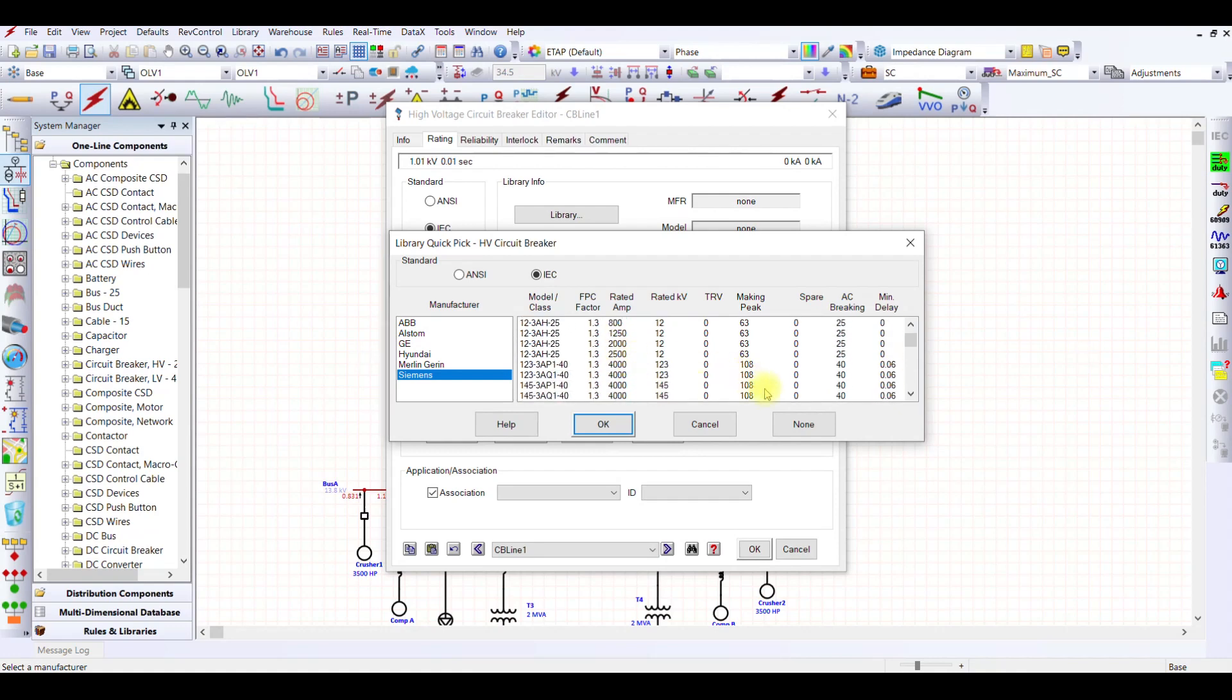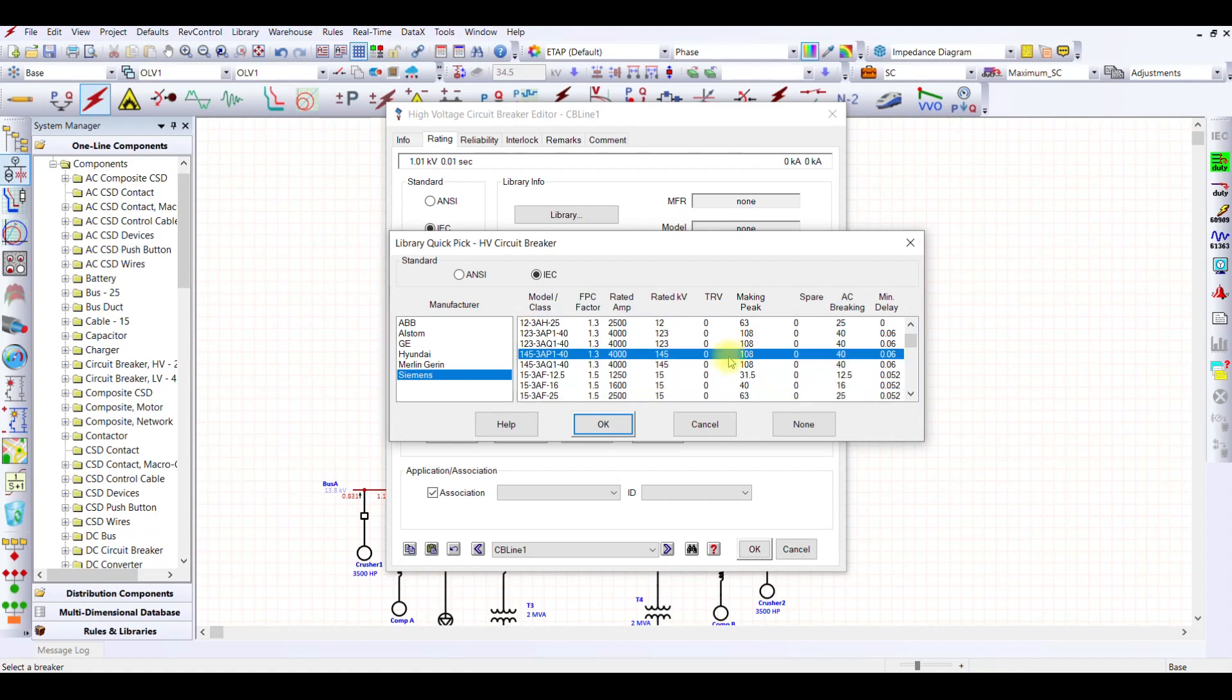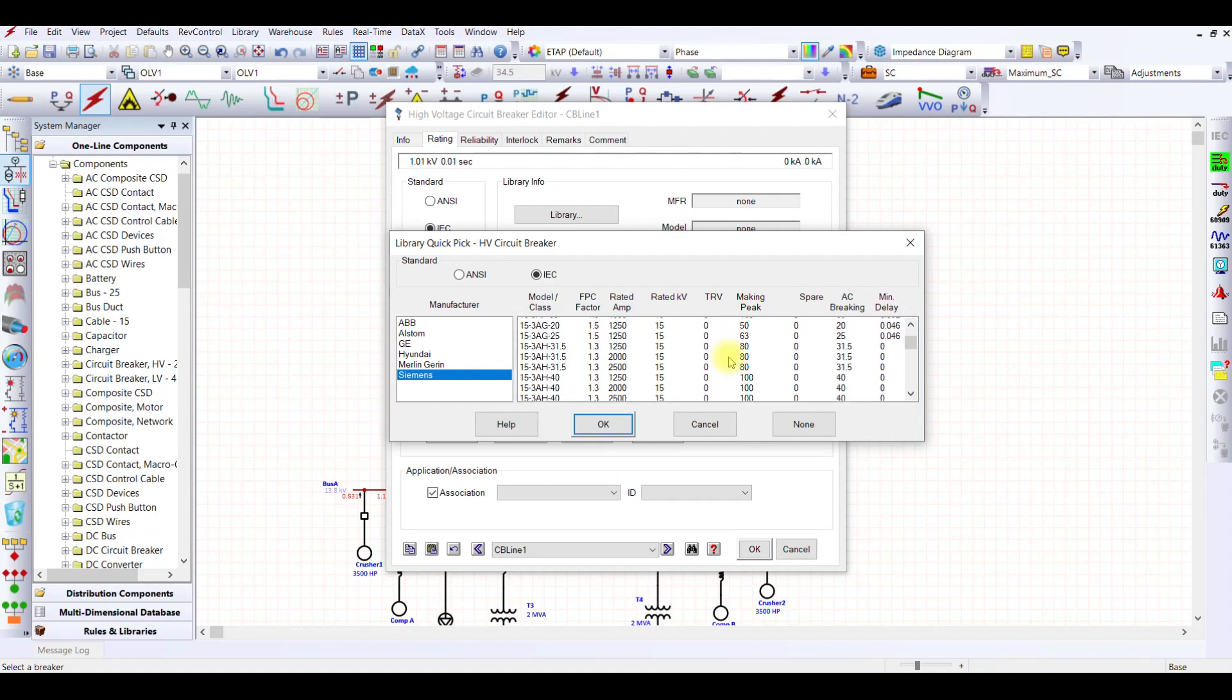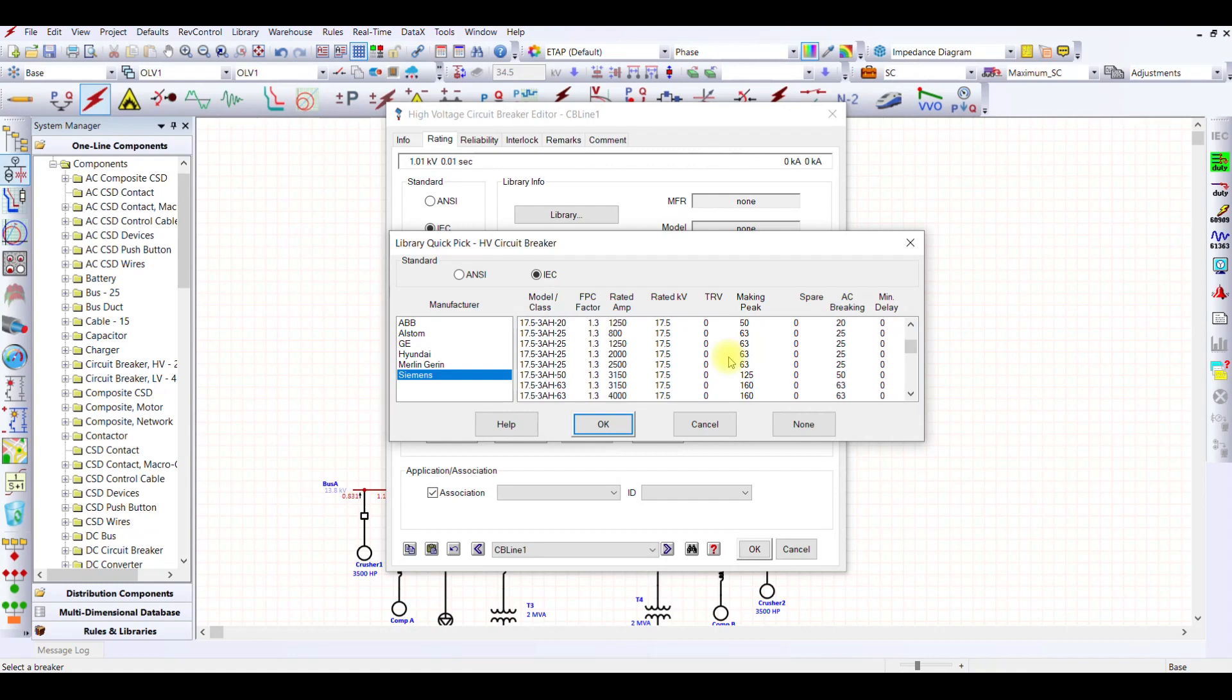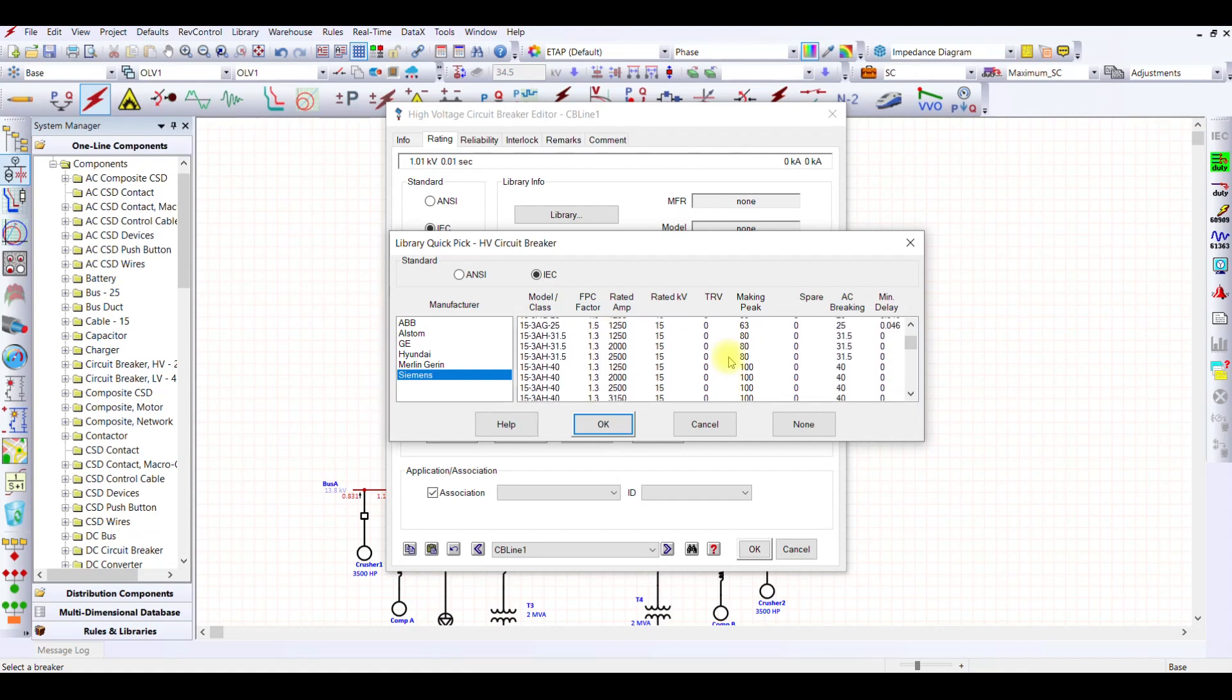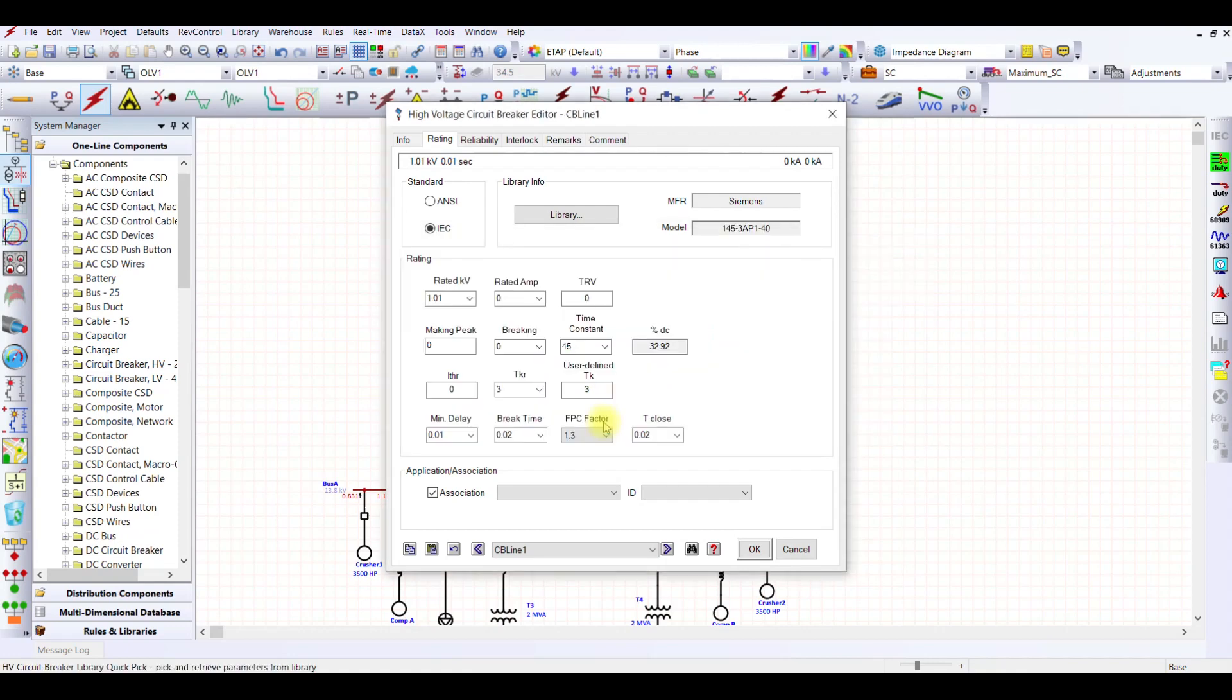145 kV, we have the making capability. Let's select this breaker because it has an AC breaking capability of 40 kA. This seems good to me. I select this Siemens 145.3 AP1.